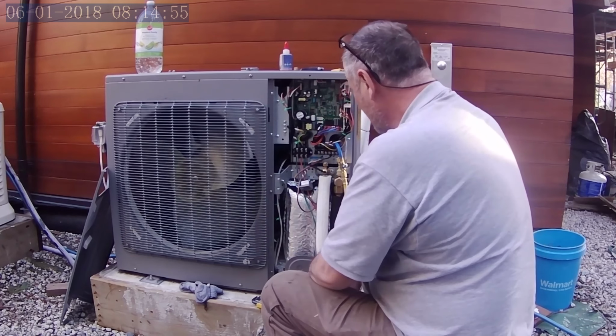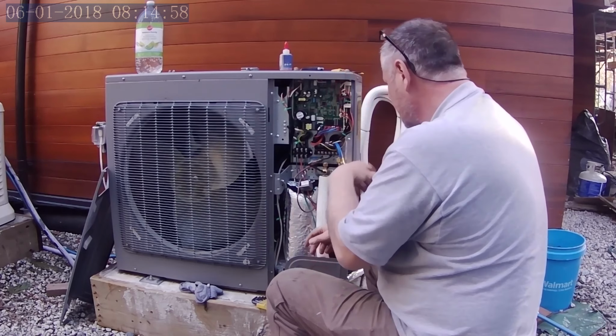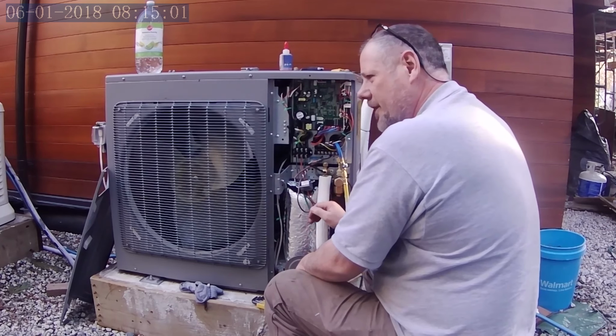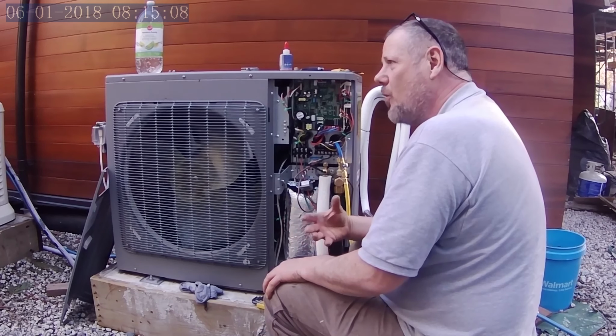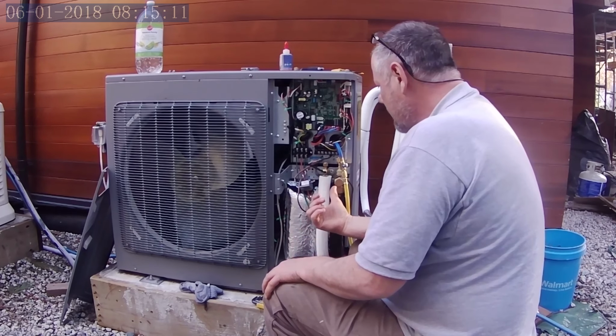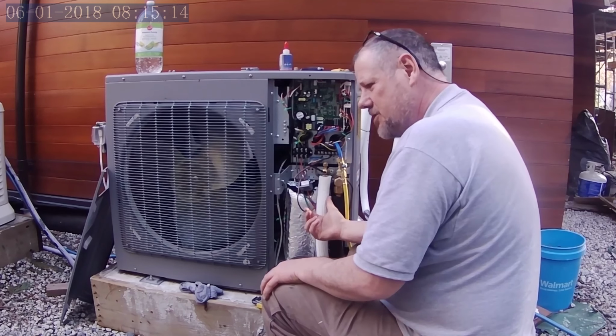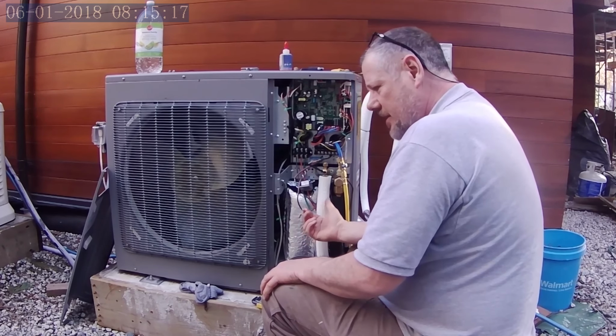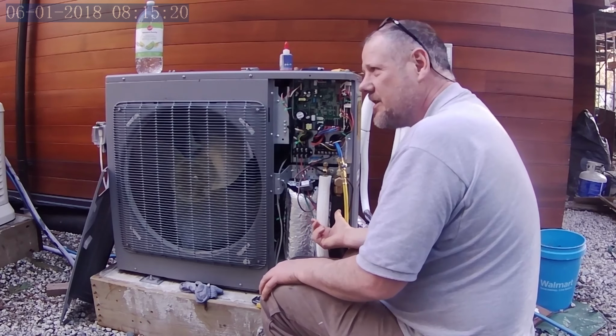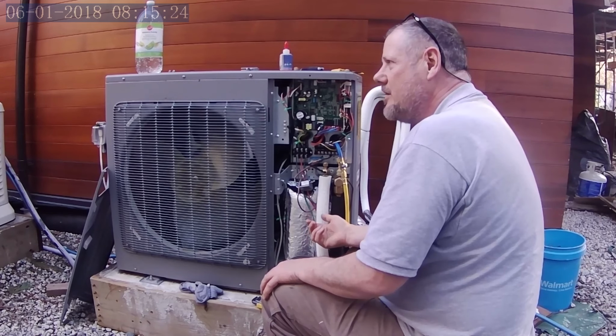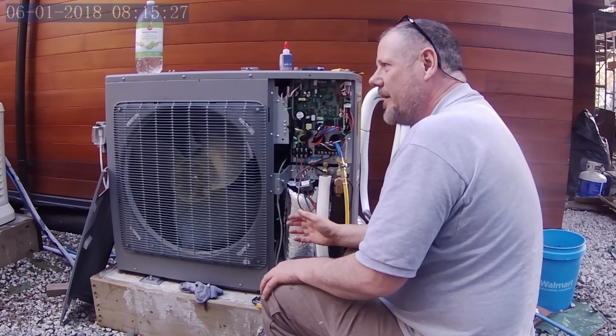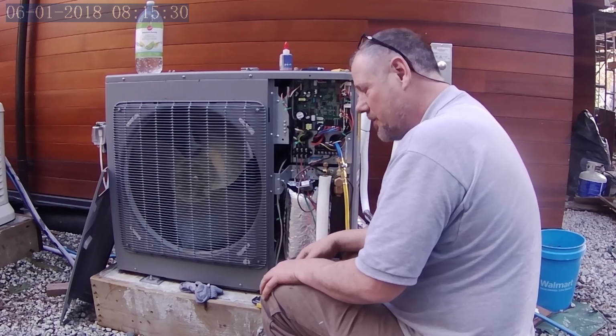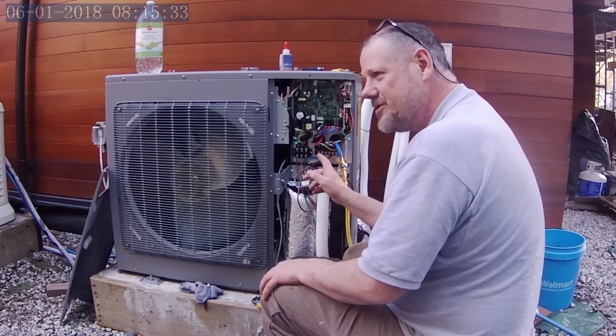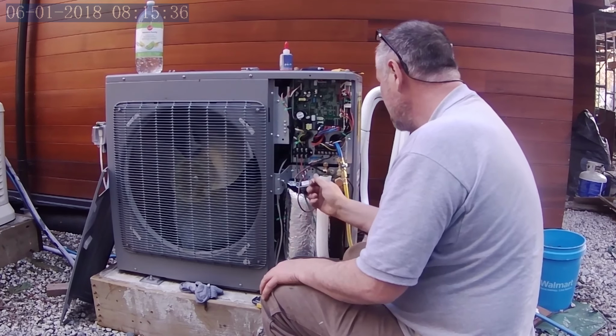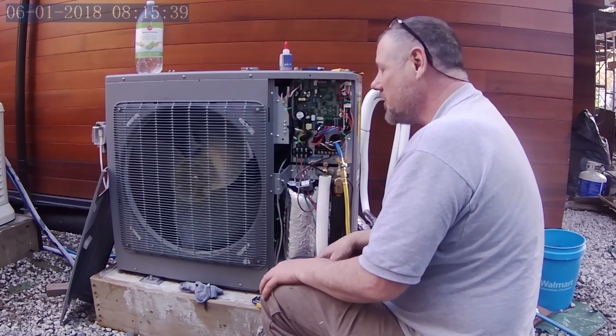Okay, I can hear it now going through. I'm going to open it really slowly. So Benoit told me to open the liquid line first, because it's a two-part refrigerant oil, you want it to mix properly. But on the various YouTube channels with the technicians, they sometimes recommend opening the suction line, because if you open the liquid line, apparently you can have the oil come out of the compressor. So to counteract that, you just open it really slowly, if you are going to be opening the liquid line for 410A.